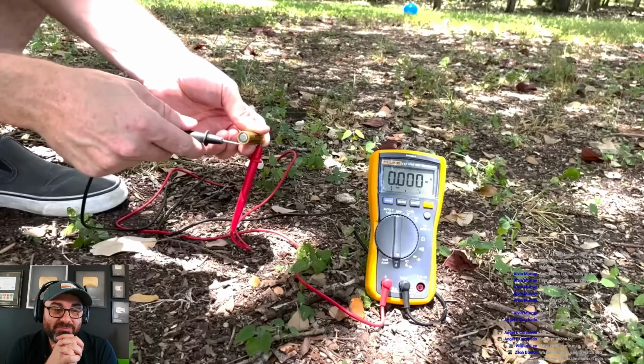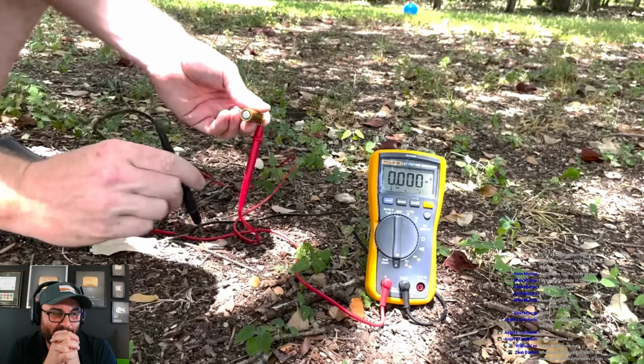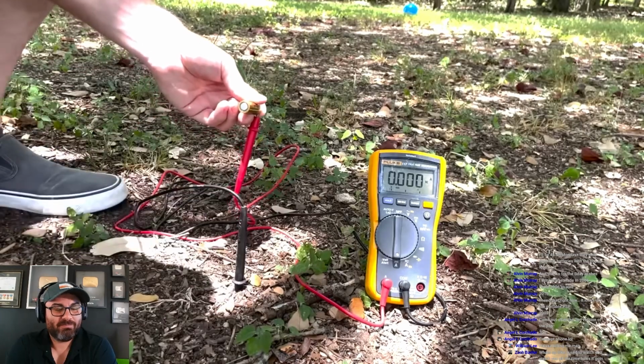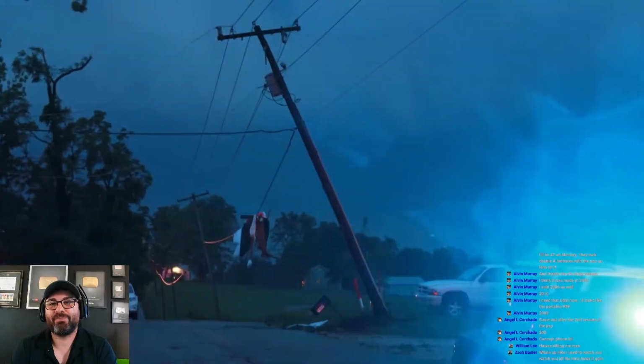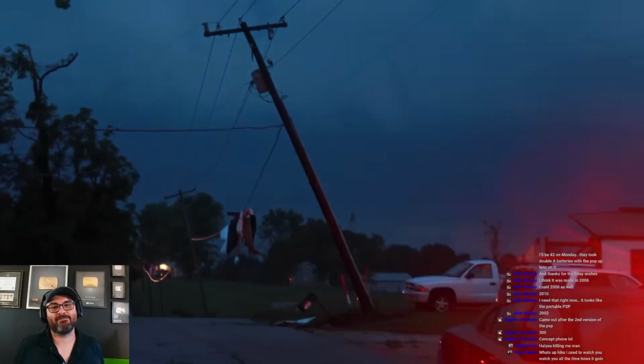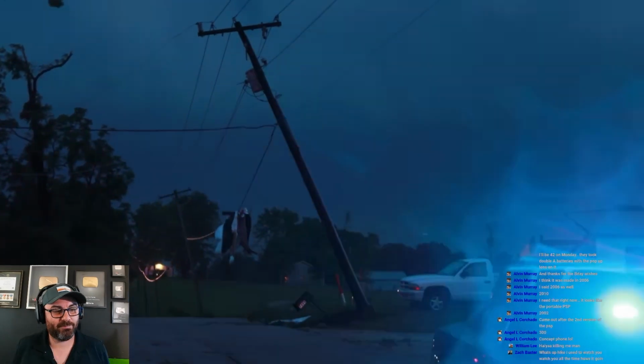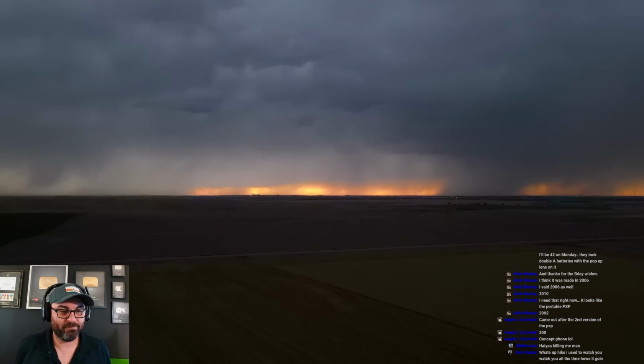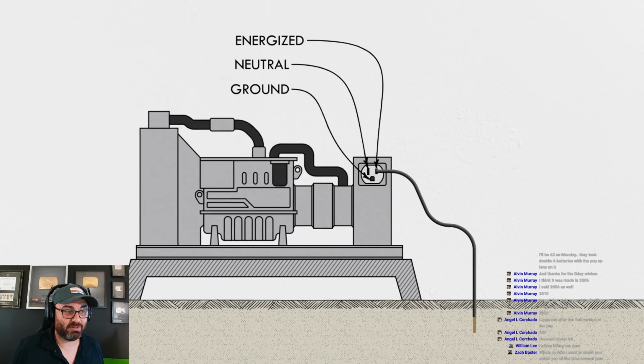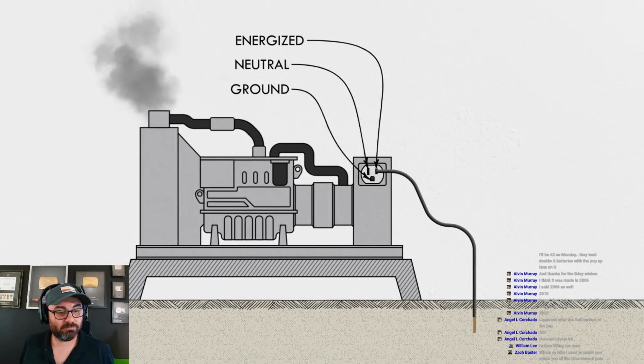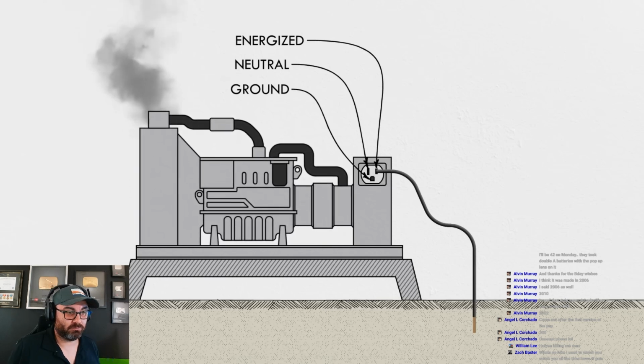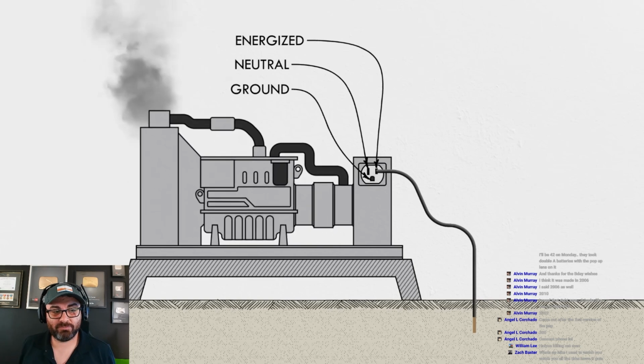For example, if I run a wire from the positive side of a battery into the ground, nothing happens. But when an energized power line falls from a pole, there's definitely current flowing into the ground then. Cloud to ground lightning strikes move huge electrical currents into or out of the earth. But my little thought experiment of a generator connected to a grounding electrode won't create any current at all. I'll explain why in a minute.